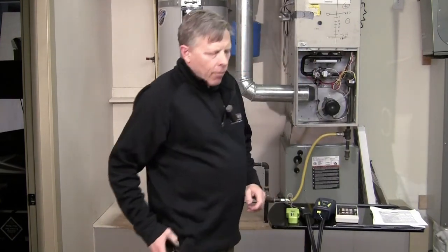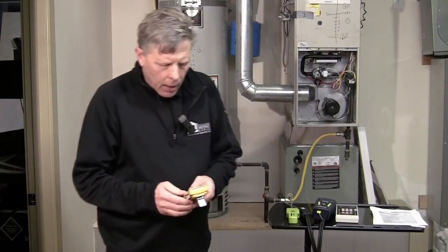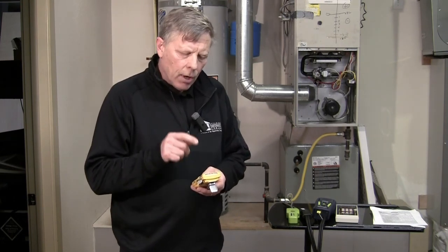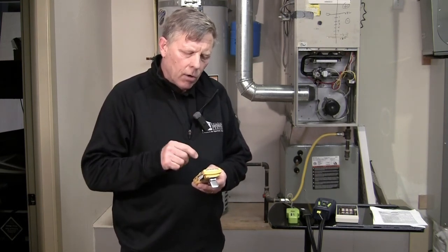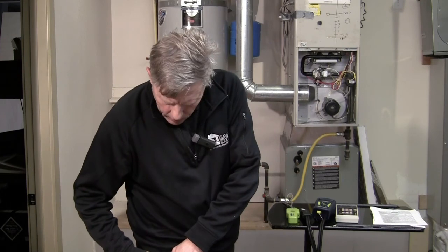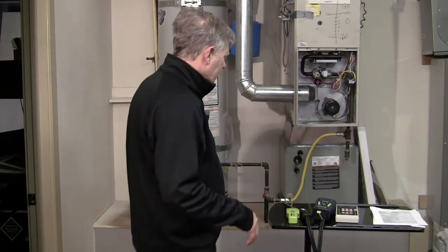Okay, I'm walking in from the front porch and I'm going to check with my 4-gas monitor whether we have acceptable limits of ambient CO and acceptable percent LEL, and it looks like I have 0 ambient CO and 0 LEL, so we're good to continue testing. We do have a safe environment. I'm going to clip this to my belt to monitor those 2 things while we're testing.